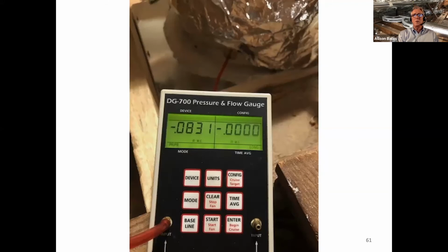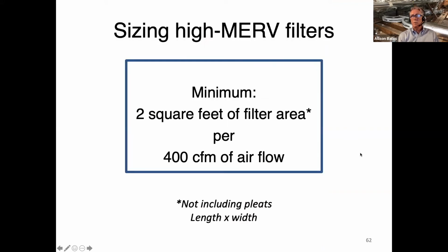But first, how I got to this low pressure was a simple rule. In our design, we use 2 square feet of filter area for each 400 CFM of airflow. So 2 square feet per ton, basically. The 400 CFM is nominally a ton of airflow. It's the airflow for 1 ton of capacity. And the 2 square feet, as I say down here, is just the length times the width of the filter. That does not include all the pleats. It doesn't include the stretched out area of the filter fabric. That's just length times width for the frame of the filter.